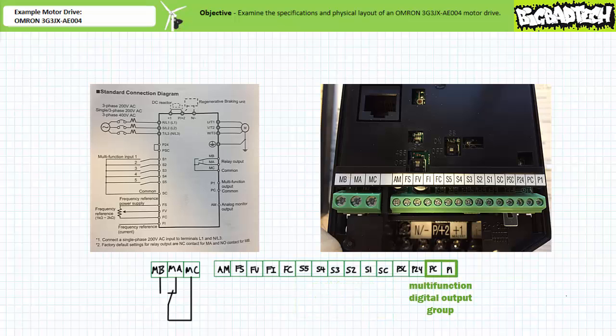Similarly, the multi-function digital output group consists of a single user programmable switched output P1 and a common PC. Depending on how the motor drive is programmed, this switched output can perform several different functions. By default, P1 is normally open; however, a user can change this deactivated state to normally closed.